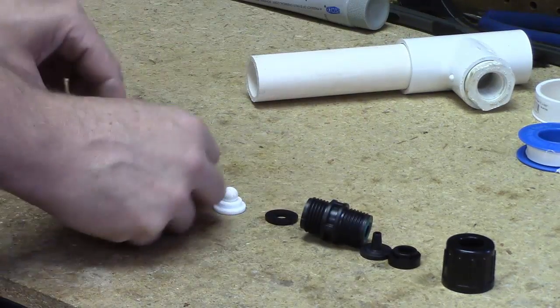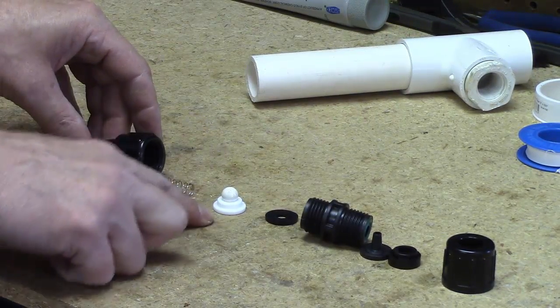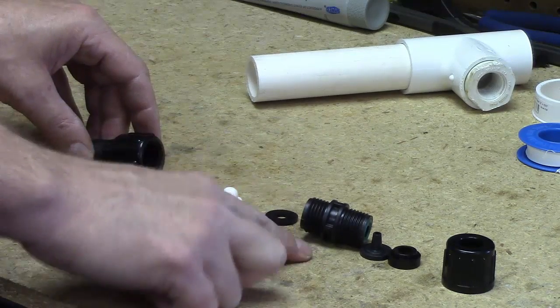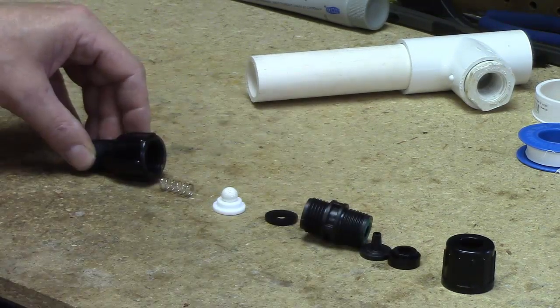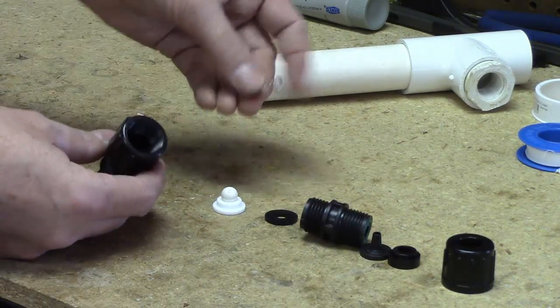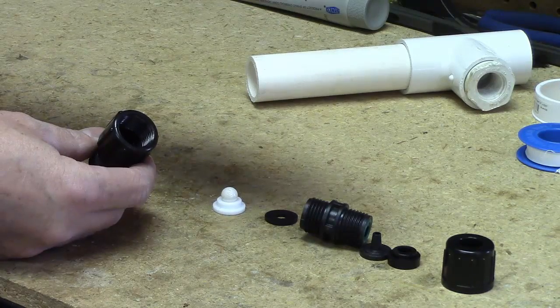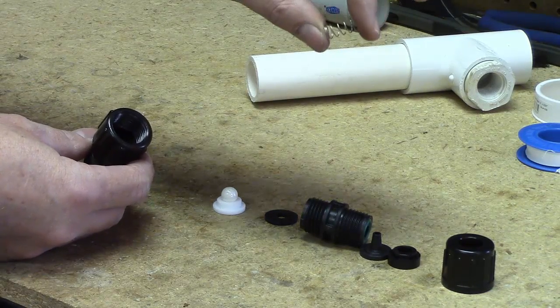So you've basically got one, two, three, four, five, six, seven, eight, nine pieces to the check valve. The spring is, if you ever have troubles with the spring, it's probably likely that a piece of debris gets in there.